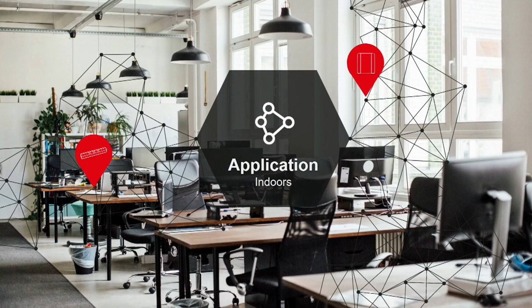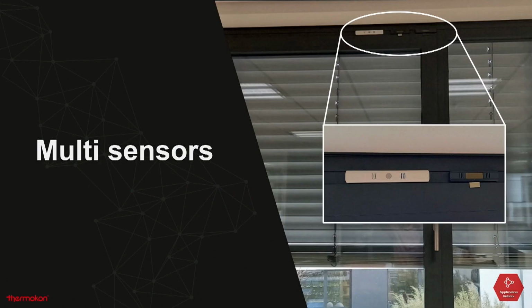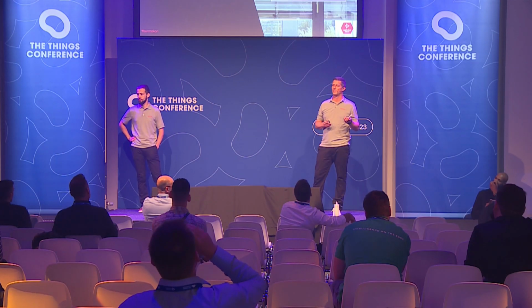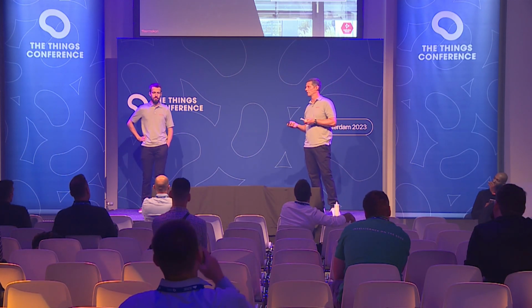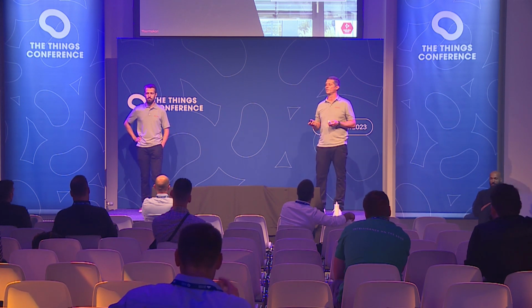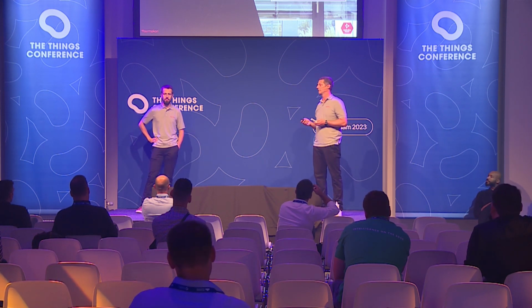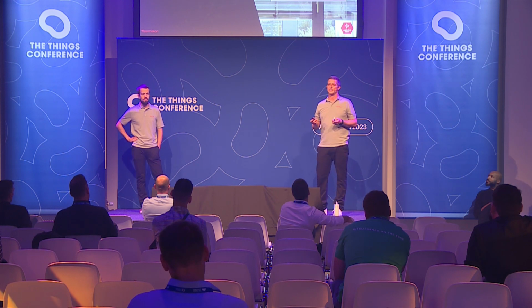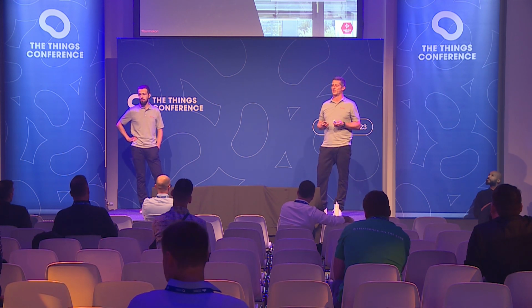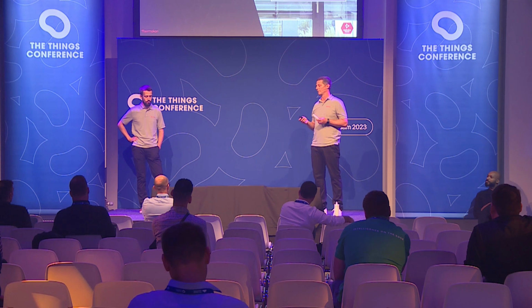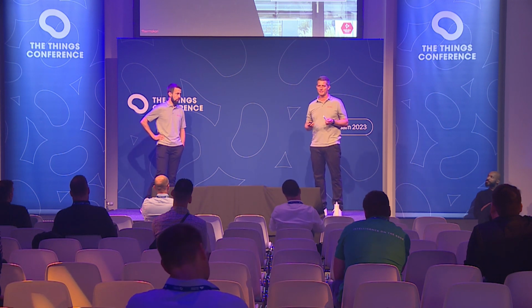Let's have a look at a typical indoor application. Currently, we see a clear trend to multi-purpose sensors. A multi-purpose sensor comes with some advantages and also disadvantages. On the advantage side, we have less cost and less installation and integration work. The disadvantage is that the installation place is not the best one for every value.